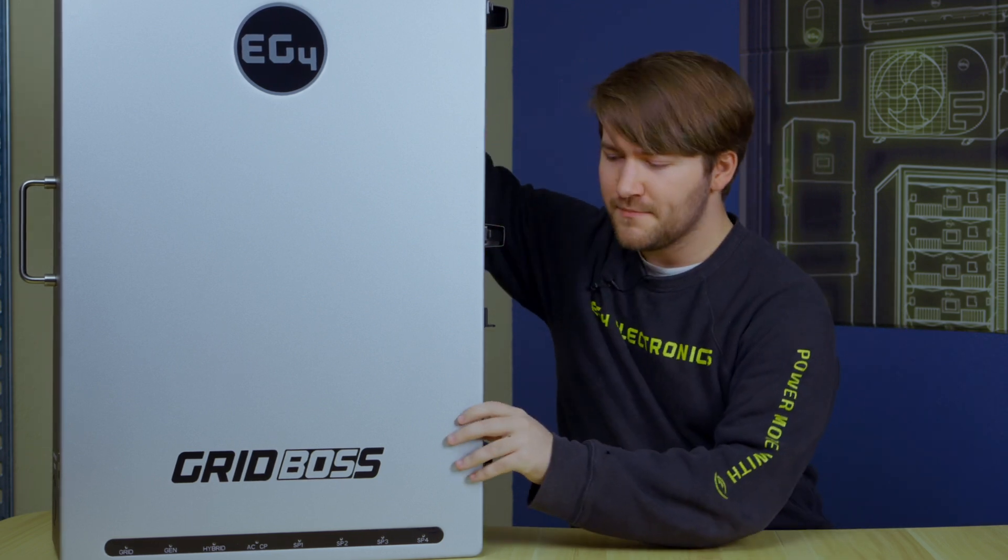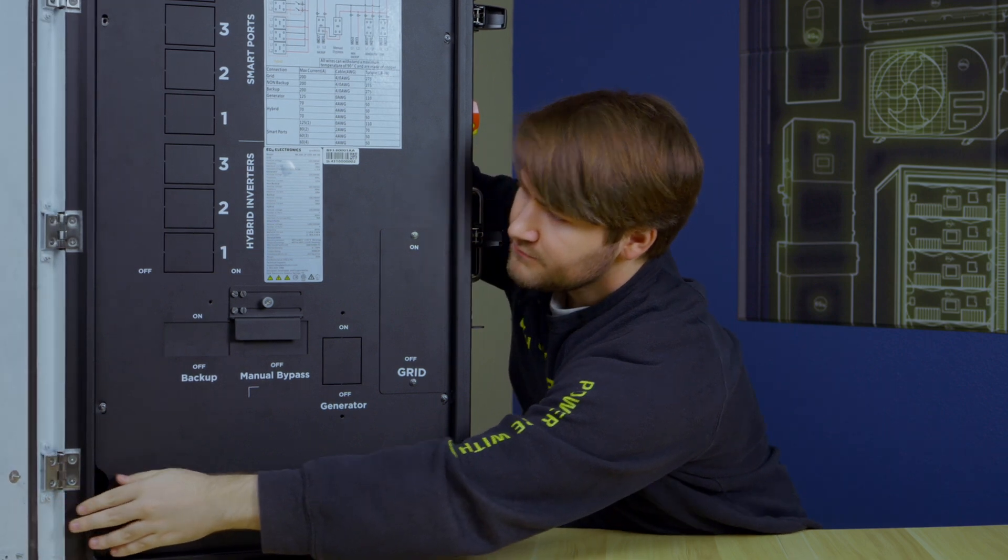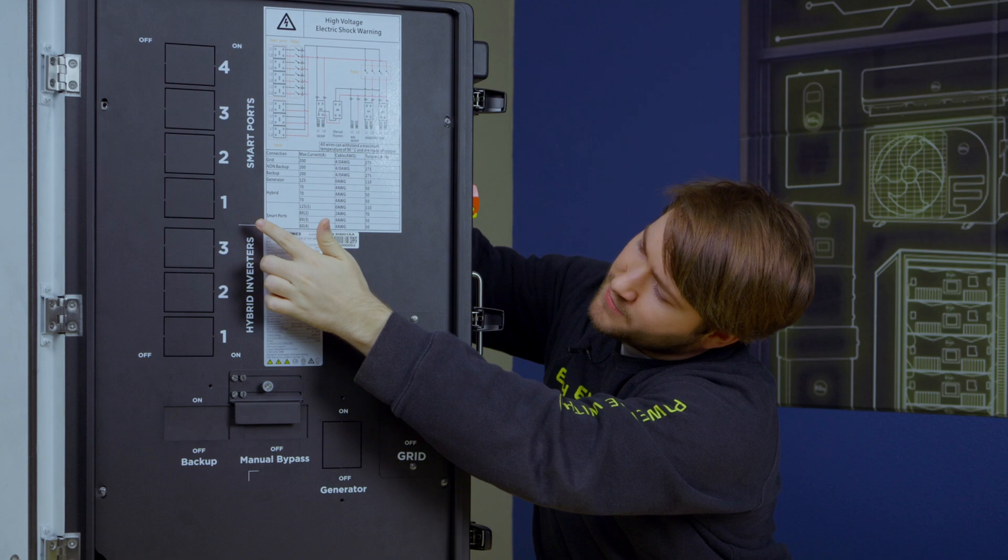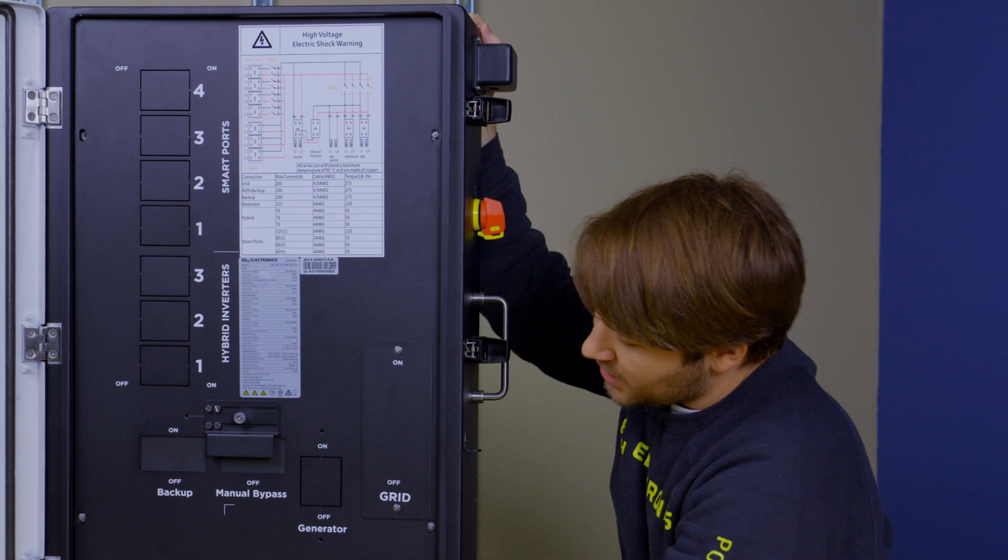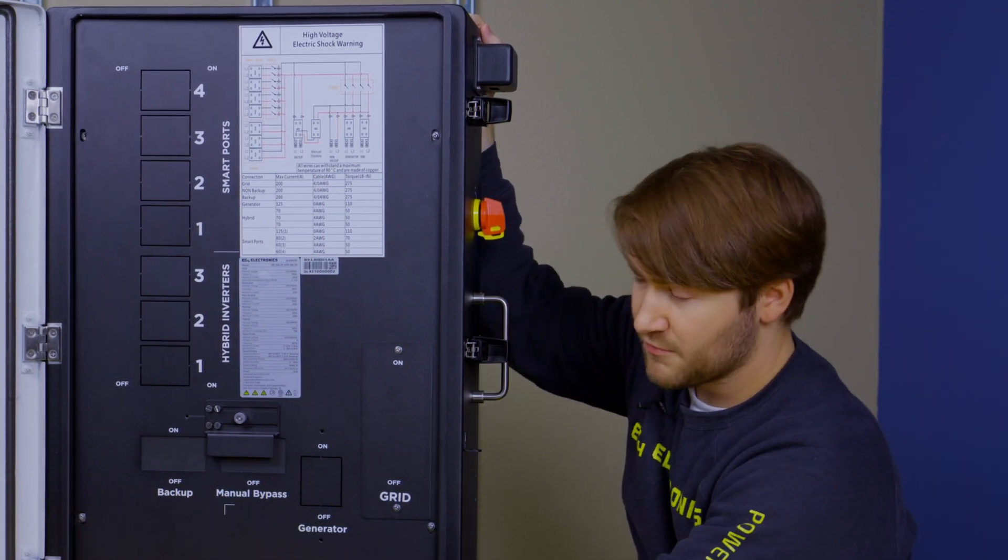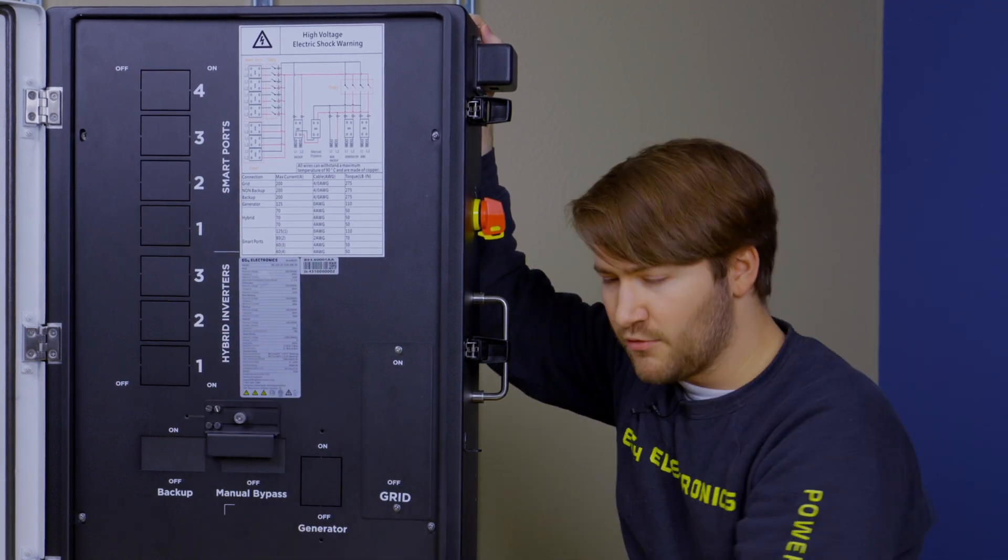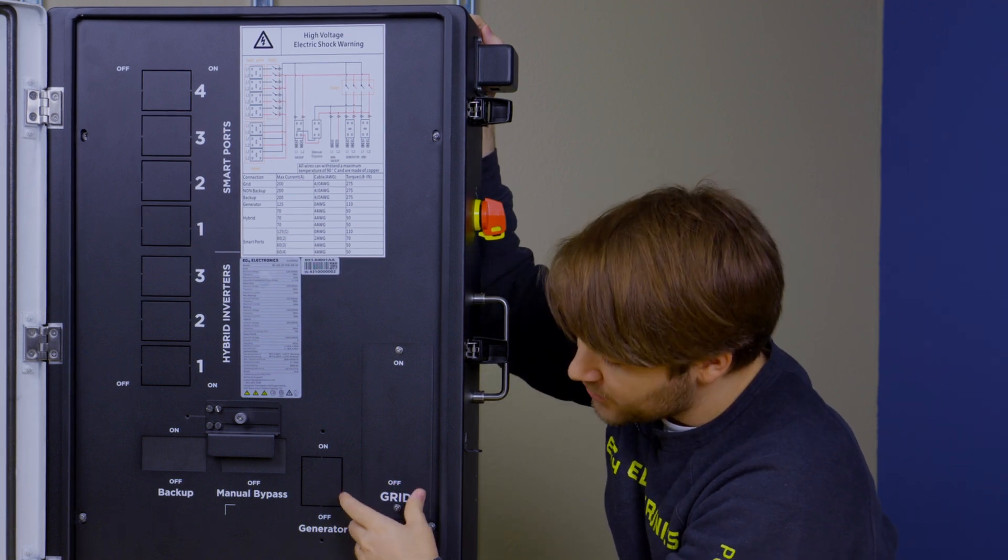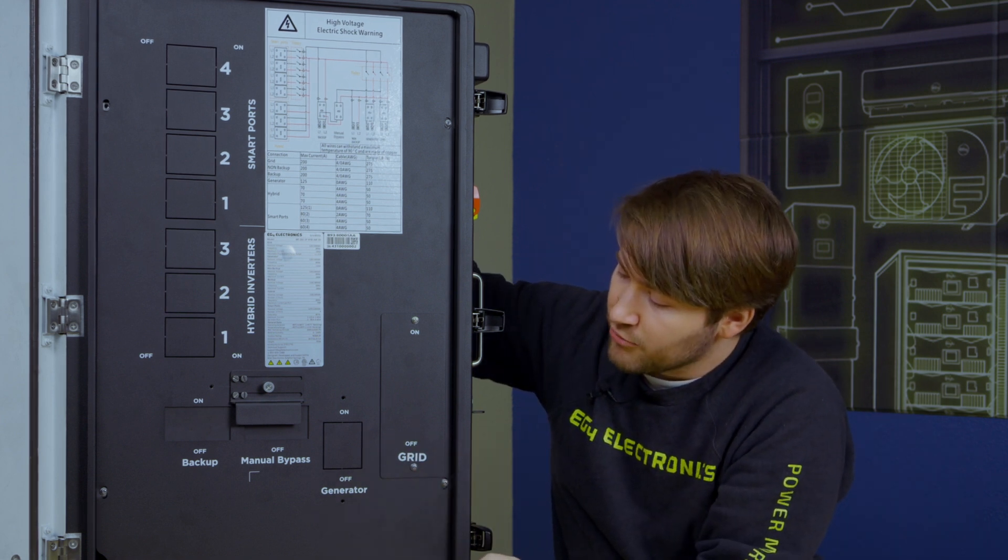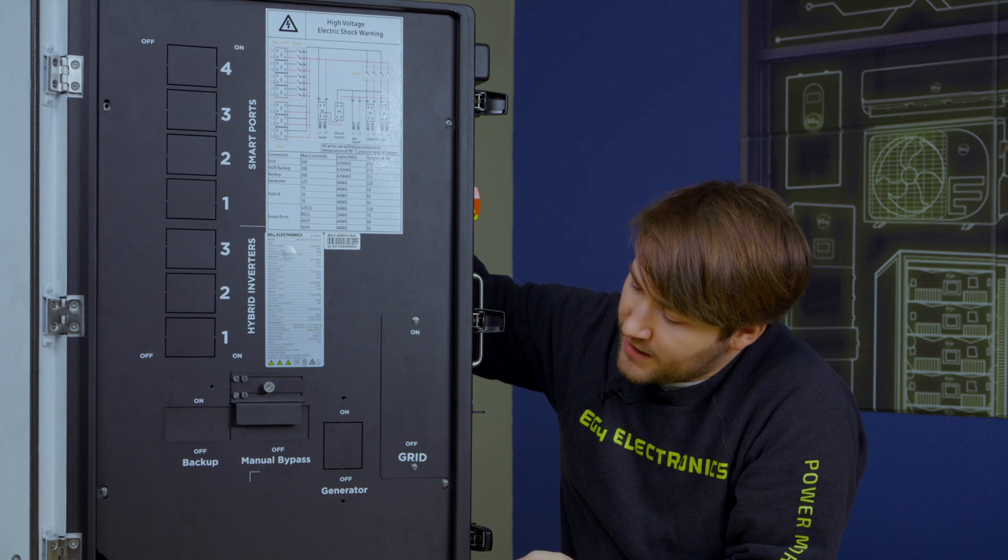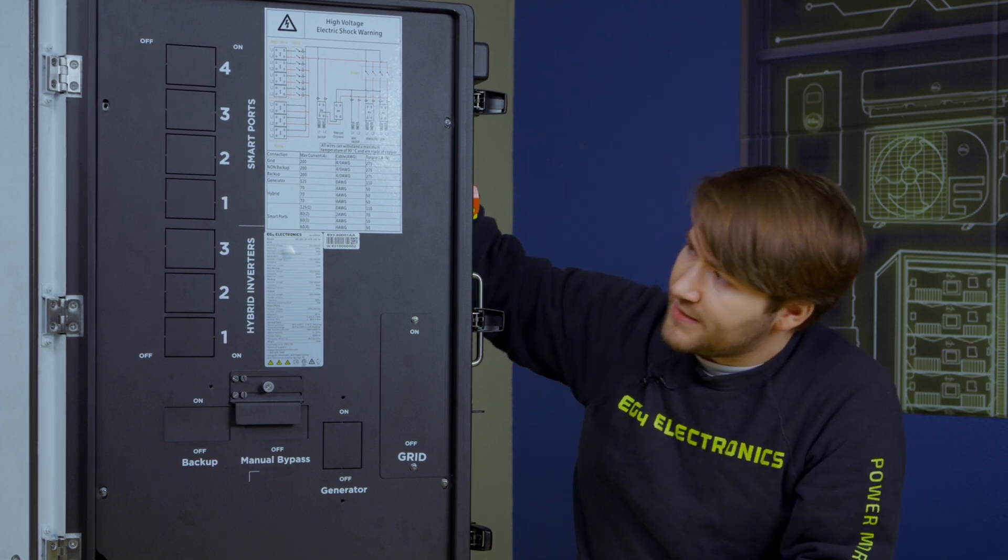So let's go ahead and crack this open. Here on the inside, we have four smart ports from the top down, three slots for hybrid inverters. We have a breaker slot for backup versus manual bypass, which the backup would be tied to the output of the hybrid inverters, and then manual bypass would be a direct to critical loads from the grid, which has a panel right here that you can take off and fit with the appropriately rated grid breaker. And then we also have a generator breaker slot if you want to add one of those in.